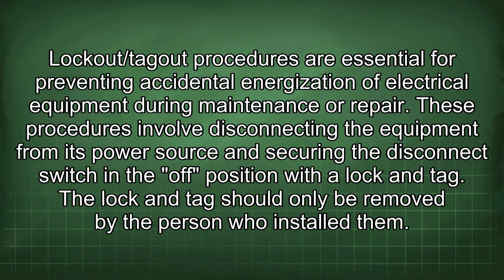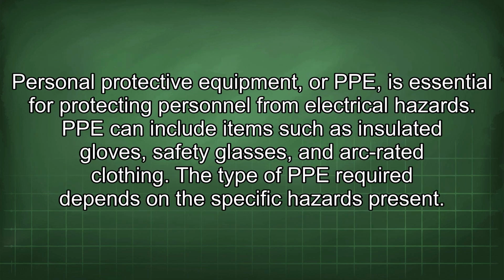Lockout/tagout procedures are essential for preventing accidental energization of electrical equipment during maintenance or repair. These procedures involve disconnecting the equipment from its power source and securing the disconnect switch in the off position with a lock and tag. The lock and tag should only be removed by the person who installed them. Personal protective equipment, or PPE, is essential for protecting personnel from electrical hazards. PPE can include items such as insulated gloves, safety glasses, and arc-rated clothing. The type of PPE required depends on the specific hazards present.